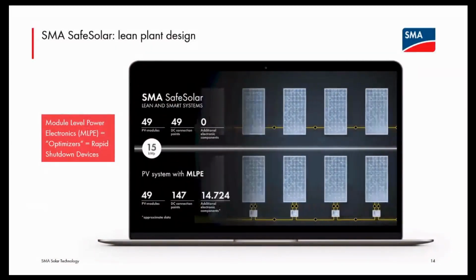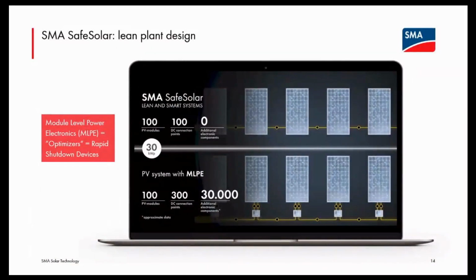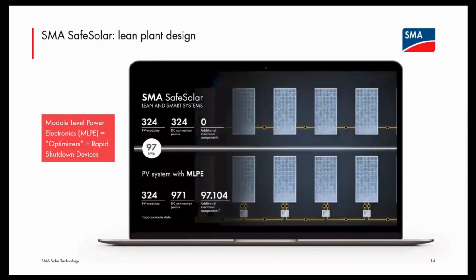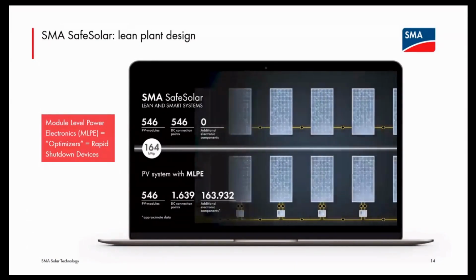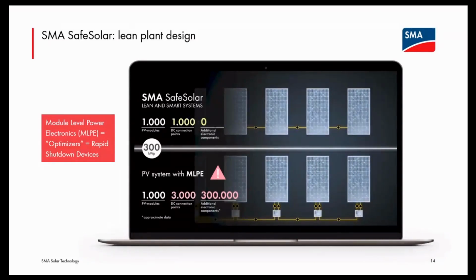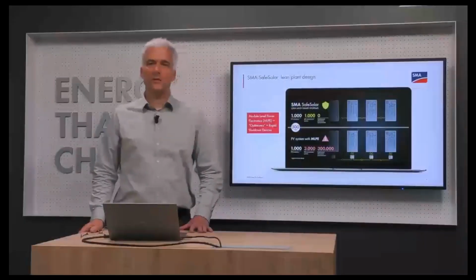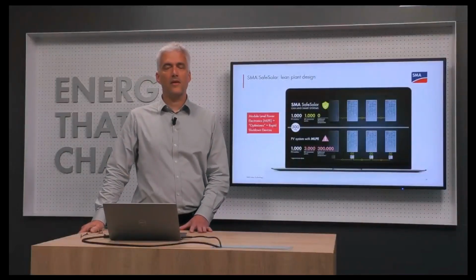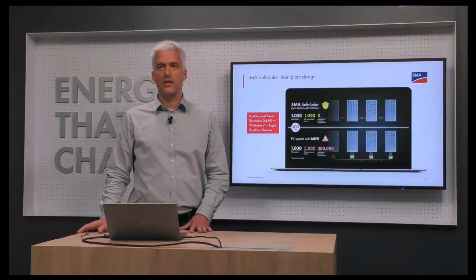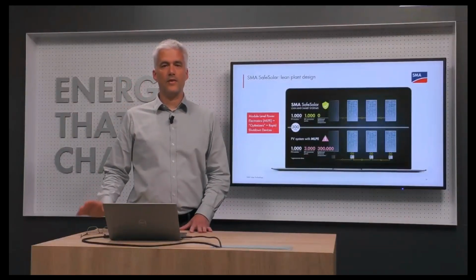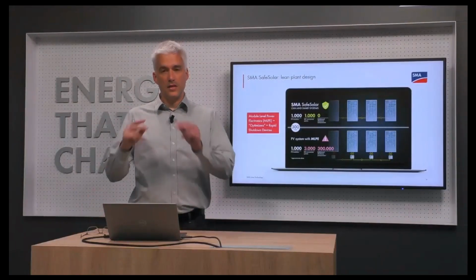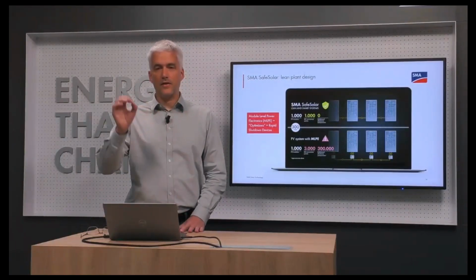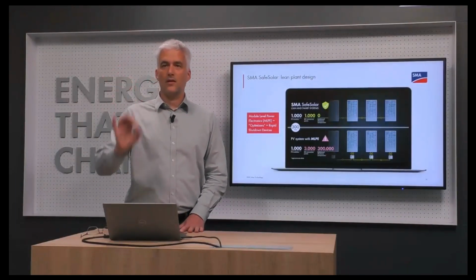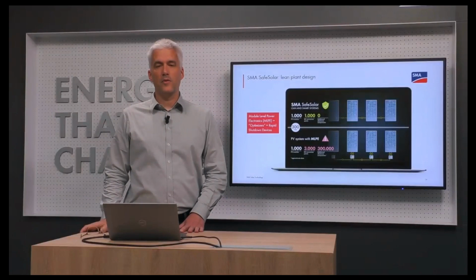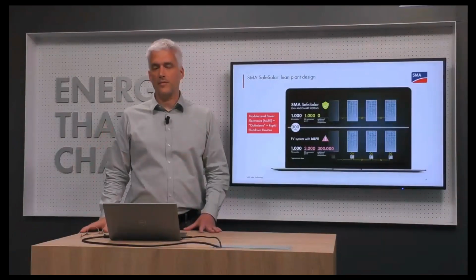There's a 10 kilowatt peak system, a 30 kilowatt peak system, 100 kilowatt peak system, 300 kilowatt peak system. It could all go on and on, but I stop it here. And let's look at the results. For a 300 kilowatt peak system, you've got roughly 1,000 PV modules. For a string inverter system, you've got 1,000 points of interconnection. And those interconnections are done with connectors from the same manufacturer, most likely manufactured on the same date, actually included with the PV module by the module manufacturer.